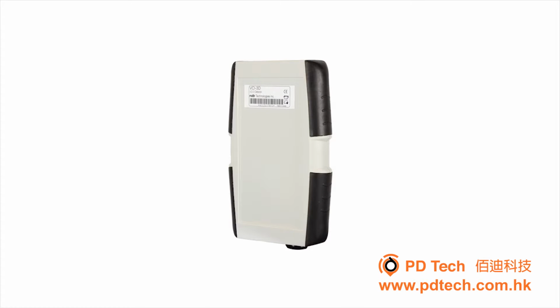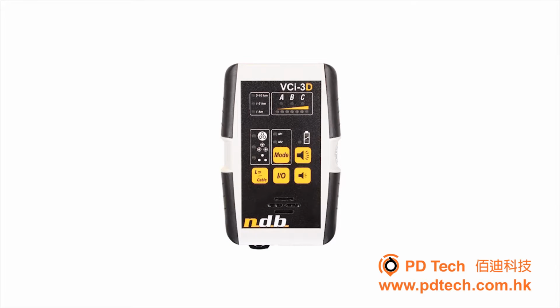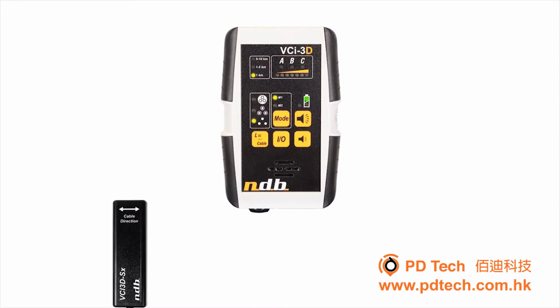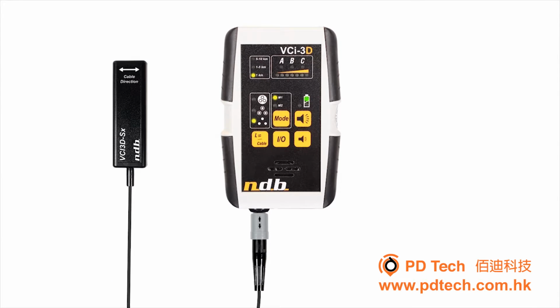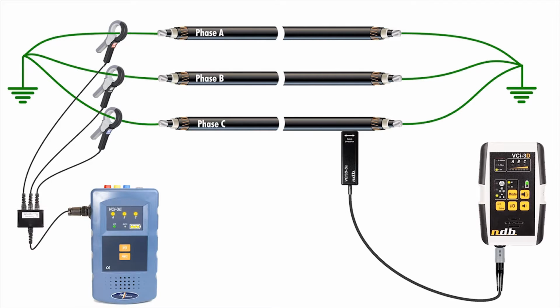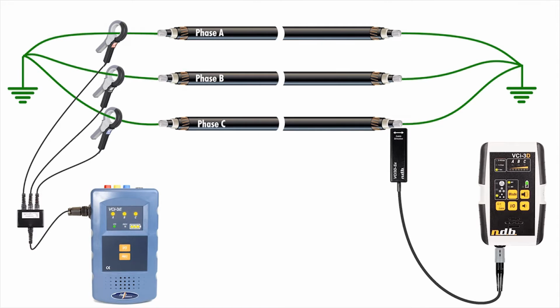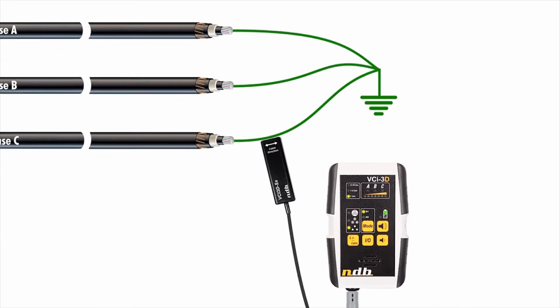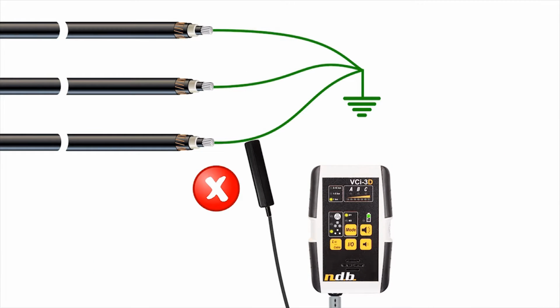The VCI-3D is a battery-operated portable detector that features adjustable gain, a built-in speaker with volume adjustment, 2 operation modes, and detection level indicators. For phase identification applications, please use Mode 1. Connect the VCI-3DSX sensor to the detector, and then apply the sensor tip on the cable. The sensor can be applied on the outer sheath, directly on the conductor, or even on the grounding leads. In all cases, the sensor position must be parallel to the cable to offer optimal performance.